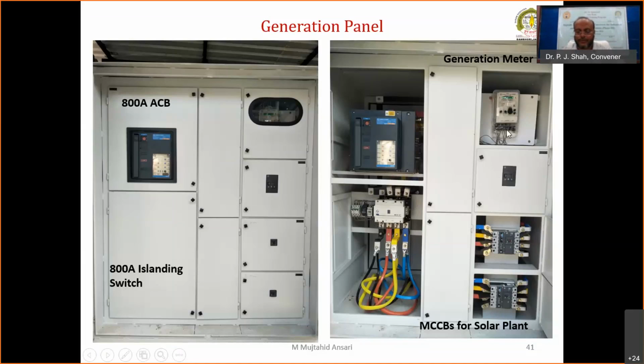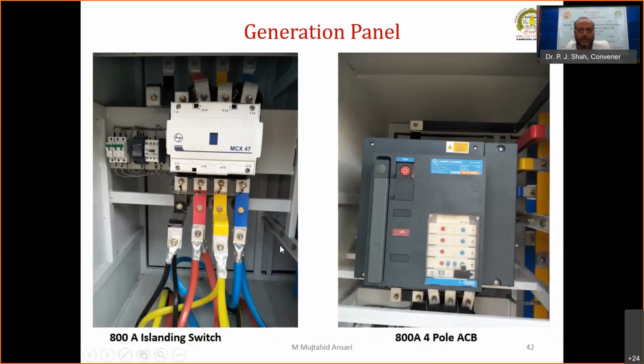generation energy meter. So this is the view: 800 ampere MCC contactor, L&T. The single phasing preventer is over this one with an additional auxiliary contactor, and everywhere there are MCBs. So one can check by operating these MCBs, or MSEDCL, when they give permission, the testing team is going to perform the islanding test with the help of these MCBs. So this is the 800 ampere ACB.